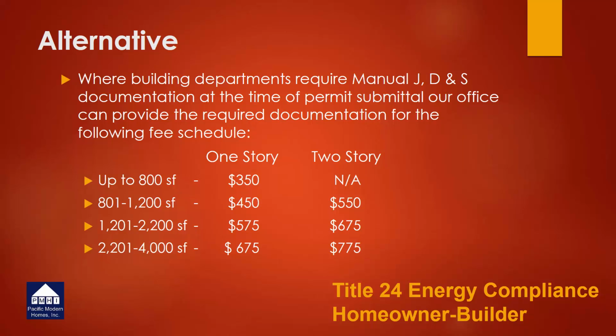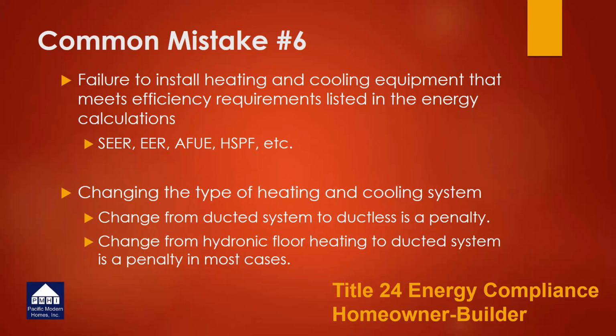So it just depends on the local jurisdiction, but we have an option here for you if you need to have it completed. Another very common mistake is when you're bidding out the heating and air conditioning equipment, the contractor comes in with a really good price, but it doesn't meet the efficiency requirements listed in the energy calculations. Typically, that is not a catastrophic failure if it's not too far different from what is shown in the energy calculations. But you need to contact our office so that we can help you verify it's not going to be a problem. In some cases, the building department may require updated energy calculations in order to make this work.